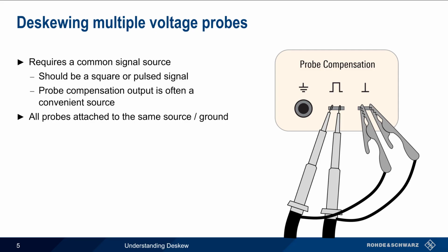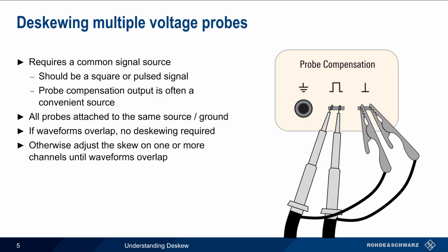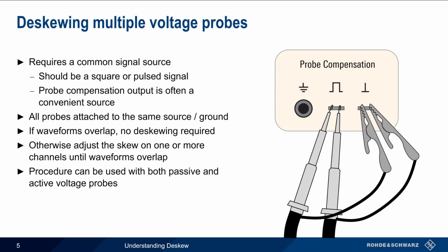As mentioned earlier, if the waveforms on each channel overlap, then no de-skewing is necessary. Otherwise, the skew on one or more channels should be adjusted until the waveforms do overlap. Note that this procedure can be used with both passive as well as active voltage probes.